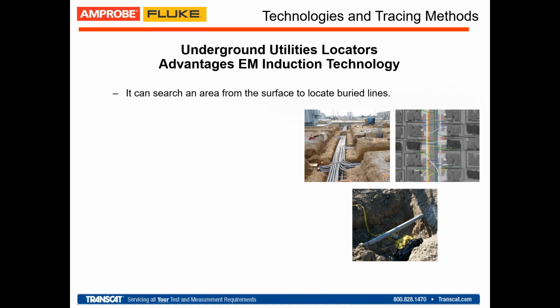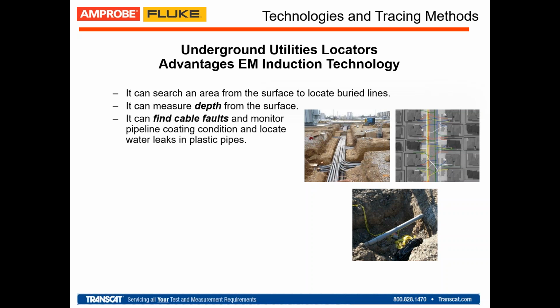An underground locator can search an area from the surface to locate buried lines. This is intuitive, but besides locating the wire or cable and estimating direction, it can also measure the depth from the surface. That's super important when estimating the depth of a utility and comparing it with the plans, since many excavation issues are driven by very old plans. It's always good to not only have the plan but compare its depth with what the locator tells you.